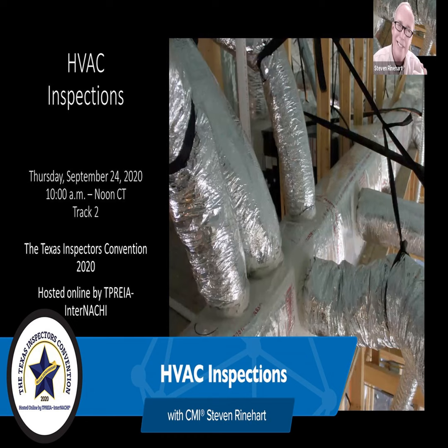There have been guys cited because they didn't make a note. It's not a deficiency to have a condensation pump. Usually you see it in a retrofit or an area where they've moved the unit and they didn't have a way to gravity drain the condensate out. You only really see them in upflows in a closet somewhere, and they neglected to put a pipe to drain the condensation. So they catch it in a pump. It's kind of like a little toilet bowl valve. When it fills up, it turns on a pump and it goes out. In theory, if it's got electricity and it works and it's not clogged up, it will pump out the water, because if you don't have electricity, the AC wouldn't be running either.